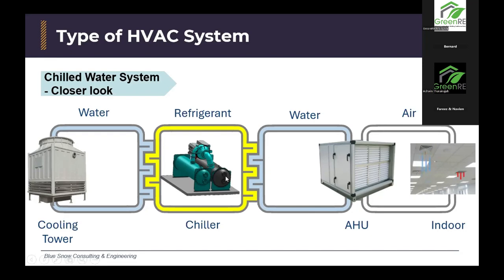The chiller still consists of the four main components, which are the evaporator, compressor, condenser, and also the expansion valve. So the heat transfers from the water to the refrigerant, and then the refrigerant rejects heat back to water and goes to the cooling tower. At the cooling tower, the water comes in contact with the outdoor air. There's a fan there that blows air through the hot water and cools down the water, and it comes back to the chiller. So it can supply cooler water to the chiller to transfer more heat from the chillers.